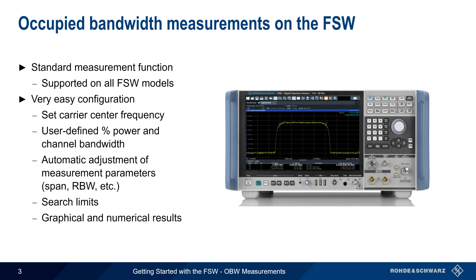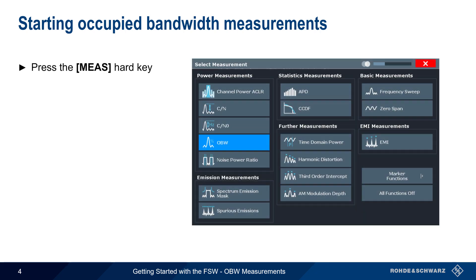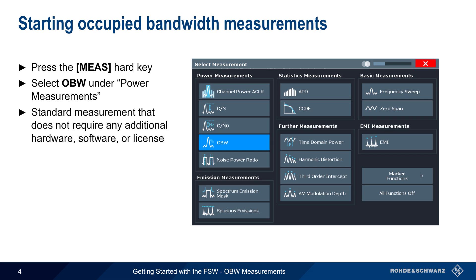In the remainder of this presentation, we'll go step-by-step through the occupied bandwidth measurement process. To make an occupied bandwidth measurement, press the Measure hard key, and then select OBW from the list of available power measurements. Occupied bandwidth is a standard spectrum measurement and does not require any additional hardware, software, or license code.